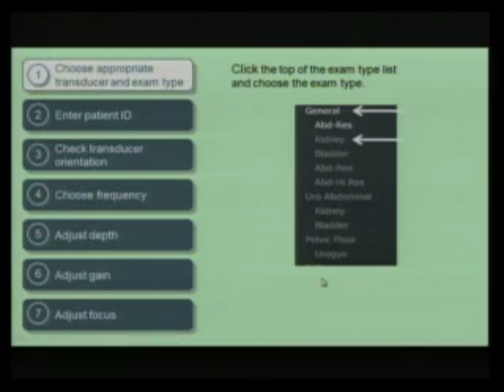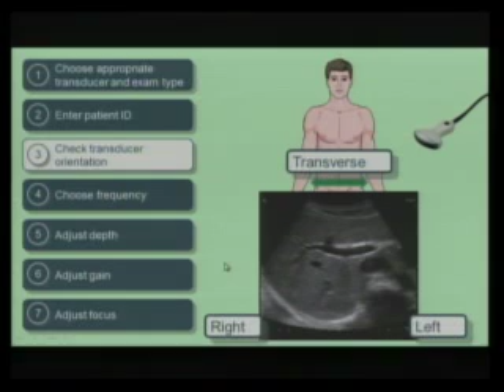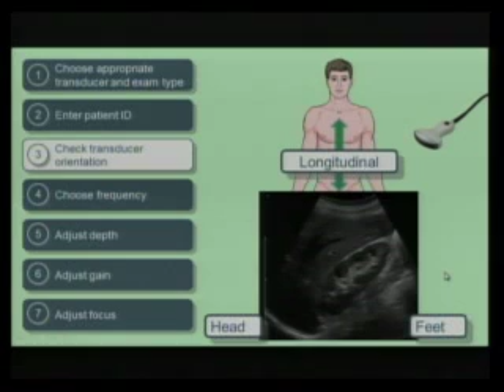The type of exam is important, and you know that you have presets about frequency and gain. Enter the patient ID, and start the exam. Check transducer orientation. This is key, especially for interventional. Transverse or axial, the right needs to be on the right, the left needs to be on the left. By convention, the right is on the left side of the screen, and the left is on the right side of the screen. And in sagittal, the head is on the left, the feet are on the right. And this seems silly, but this is all you need to see if you are oriented or not.